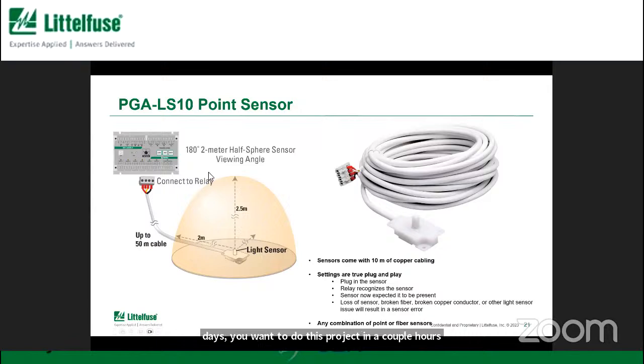These sensors are plug and play. What I mean is you plug the sensor into the relay, it will recognize it, and from that point forward, it will expect it to be there. So if the sensor itself has any problem, or the cable becomes cut, then the relay would give an alarm. You do not even need to program the relay to tell it how many sensors. It just automatically recognizes them once you plug them in.